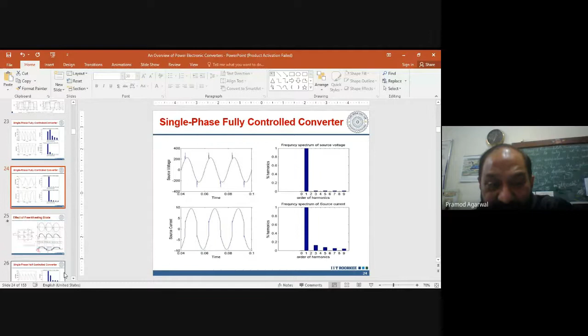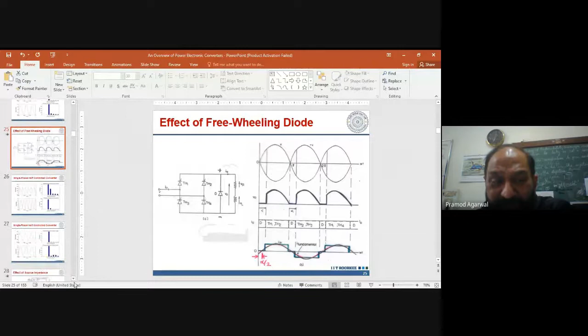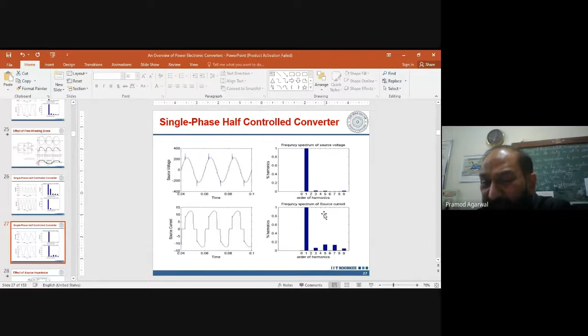If you use a freewheeling diode, you can recall that the input current becomes like this. There will be no current drawn when the voltage is 0. And in this way, if you find out the fundamental current, it is now lagging the voltage by angle alpha by 2. So input displacement factor has become cos of alpha by 2. Like that, input power factor has also improved. So the effect of the freewheeling diode is to improve the input power factor. And in the actual harmonic spectrum, output will have even harmonics and the input will have odd order harmonics. Voltage is nearly sinusoidal, but the current has harmonics.